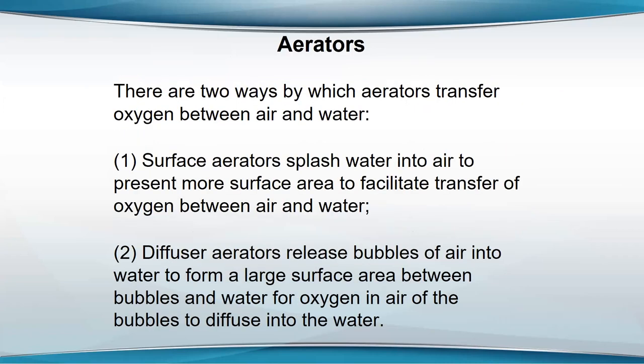There are really two ways in which aerators transfer oxygen to water. One, they splash water up into the air — spreading the water out so there's more surface for oxygen to enter. The other is they release bubbles into the water. When you splash water into the air, the aerator can't put any oxygen in the water directly — all they can do is splash water up into the air.